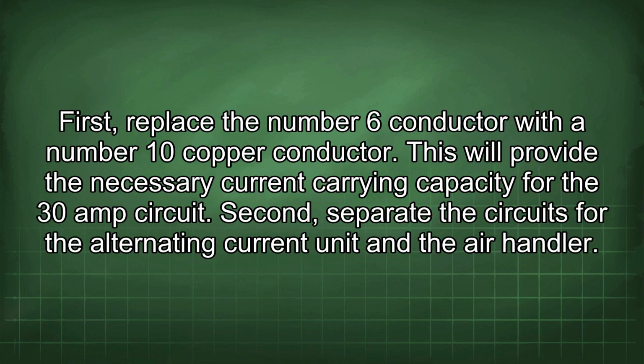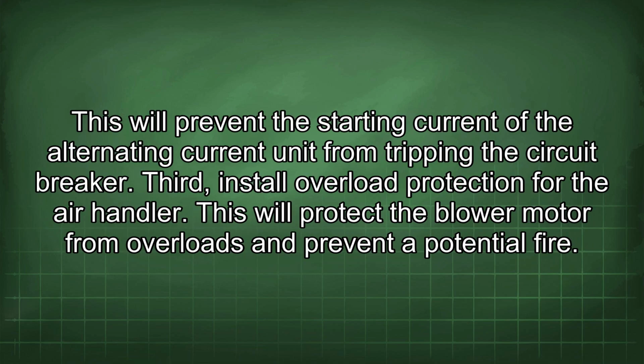First, replace the number 6 conductor with a number 10 copper conductor. This will provide the necessary current carrying capacity for the 30 amp circuit. Second, separate the circuits for the alternating current unit and the air handler. This will prevent the starting current of the alternating current unit from tripping the circuit breaker. Third, install overload protection for the air handler. This will protect the blower motor from overloads and prevent a potential fire.